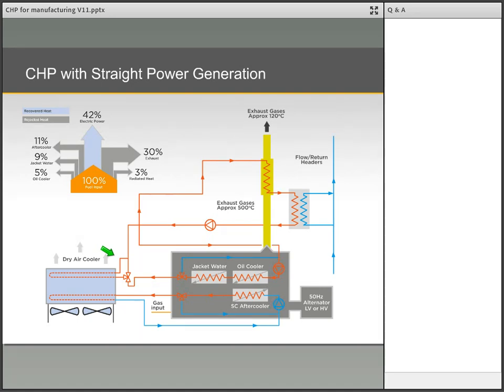The return flow is diverted to the heat rejection radiator or dry air cooler via a 3-port valve where the heat is rejected to atmosphere and the return flow cooled to the required temperature of the engine cooling system. The diagram shows the exhaust heat included in this primary circuit. With some systems, the exhaust gases can bypass the exhaust gas heat exchanger here, and the exhaust gases are put directly to atmosphere at their high temperature. This allows for a smaller radiator to be used as less heat is rejected through this primary circuit.